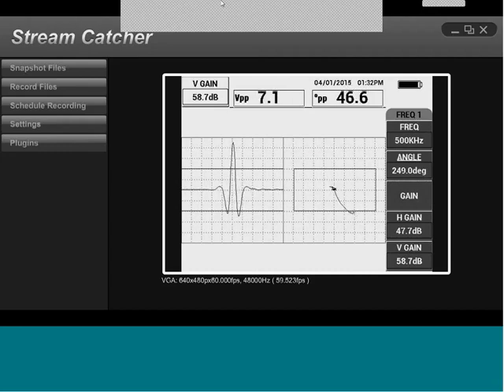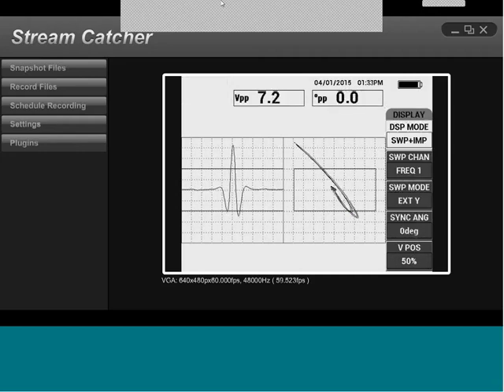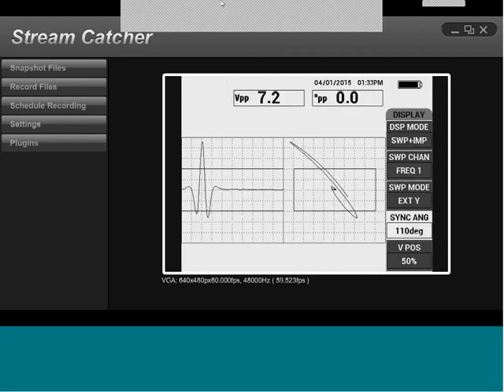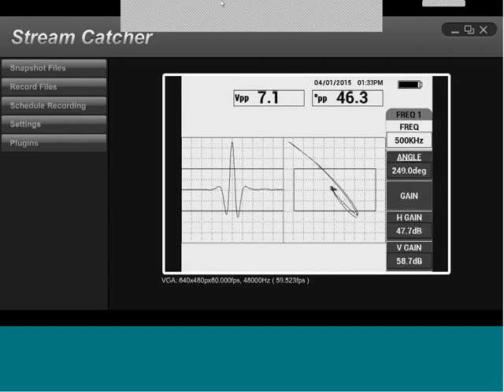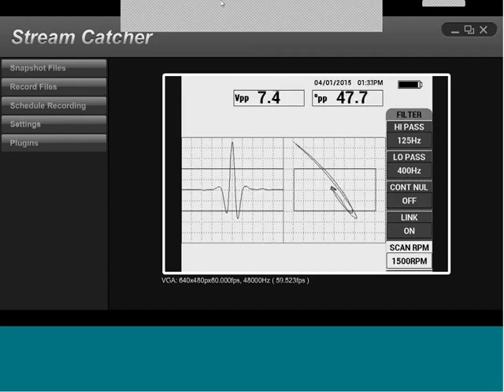While I'm maintaining this probe rotating, I want to show you that I can change my sync angle, okay, and I can delay this sweep signal. And then we can change the filters and all that nice stuff. So if I go to filters, we can see the filters. And I talked to you about the scan RPM and the link function. So right now the link defaults to on. So let's see what happens when I actually lower the speed.